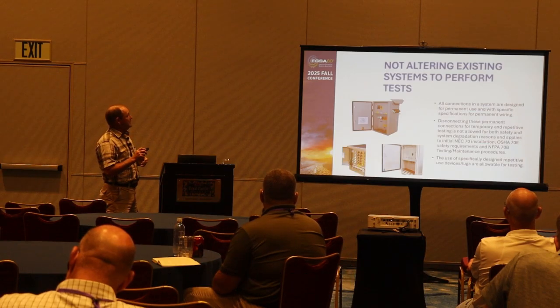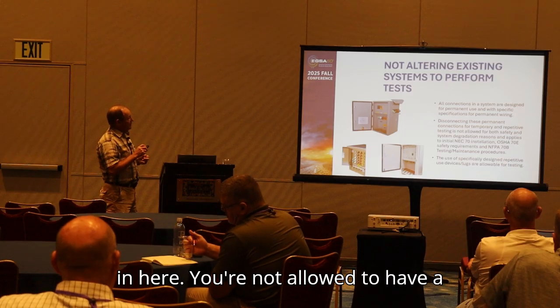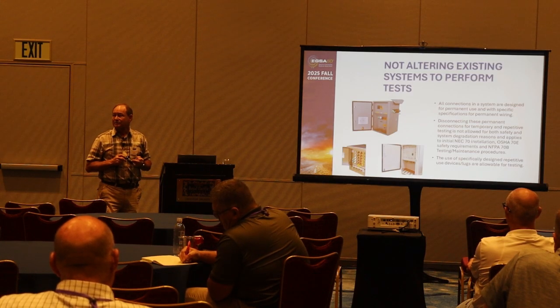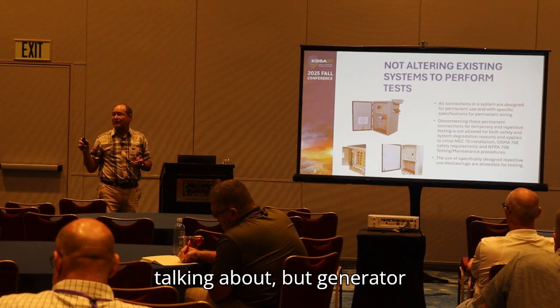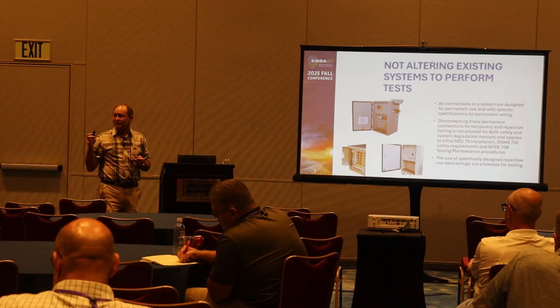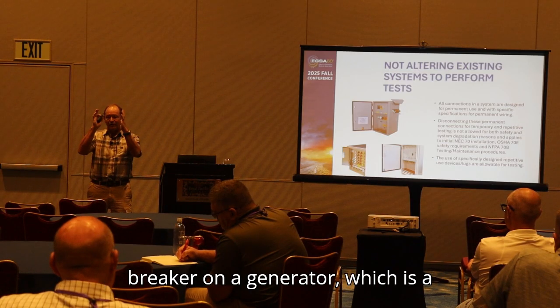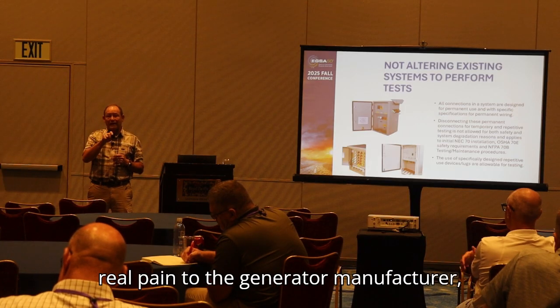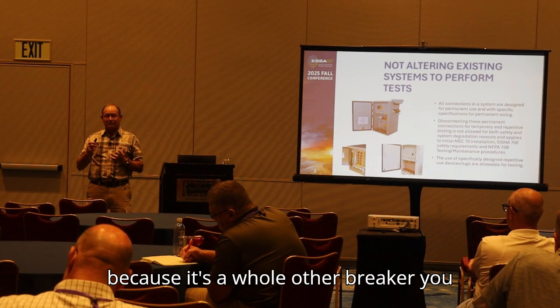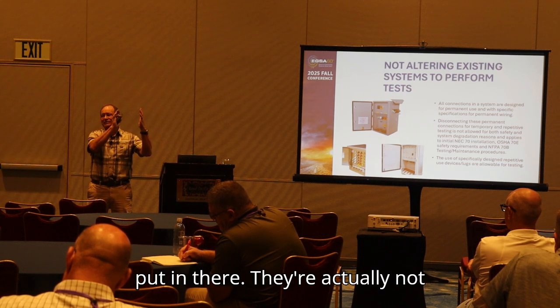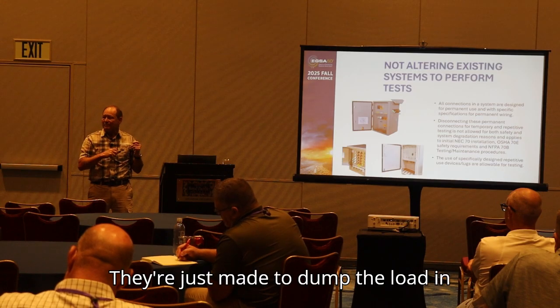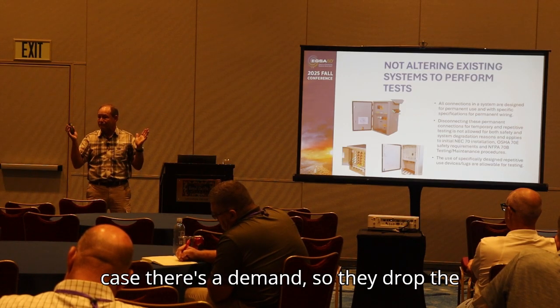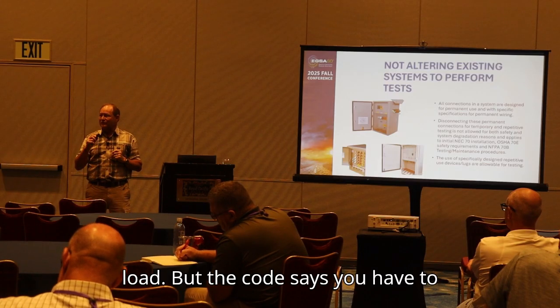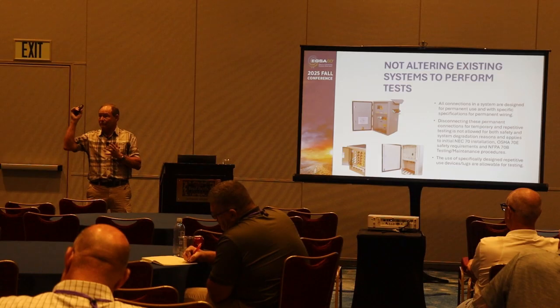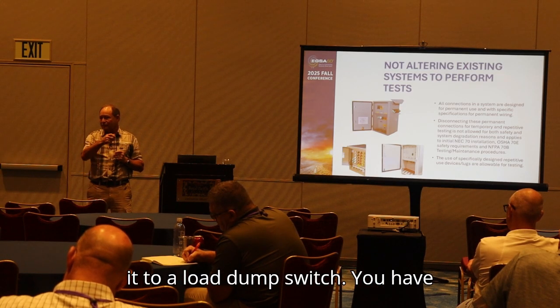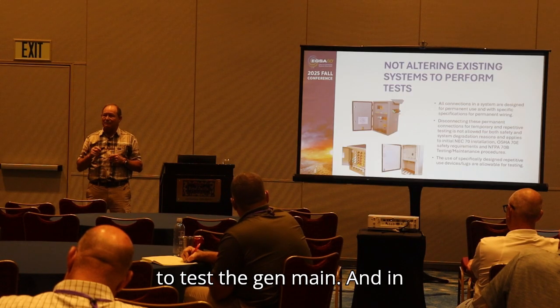And I'll tell you what I don't think is in here: you're not allowed to have a load dump breaker anymore. Some of y'all might not know what I'm talking about, but generator manufacturers would put a load bank breaker, a load dump breaker on a generator, which is a real pain to the generator manufacturer because it's a whole other breaker you put in there. They're actually not breakers, they're load dump switches. They're just made to dump the load in case there's a demand, so they drop the load. But the code says you have to test the main generator output, which is the gen main. You can't bypass it to a load dump switch. You have to test the gen main.